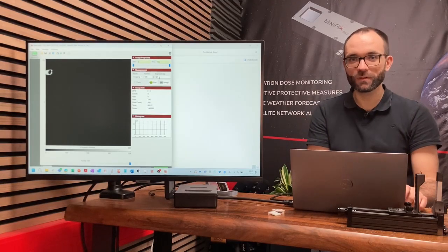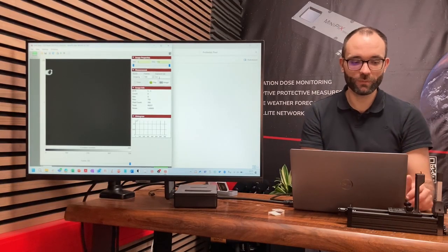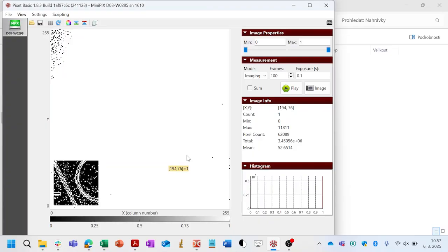As MiniPIX EDU is our cheap variant of the MiniPIX detector, it may come with certain downsides. The Advacam logo might appear in the bottom left corner. There might be some noisy or bad pixels, and there even may be a column of defective pixels. For the full list of those restrictions and to see the parameters of your device, you can refer to the datasheet of your MiniPIX EDU.